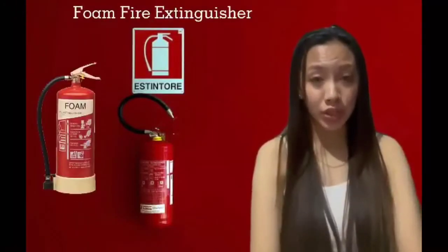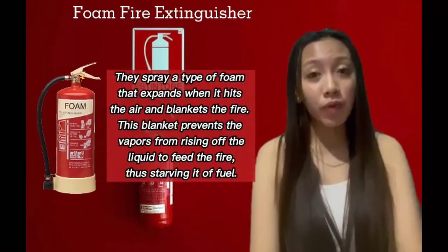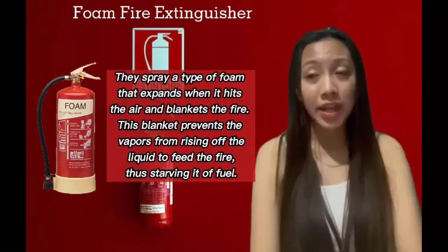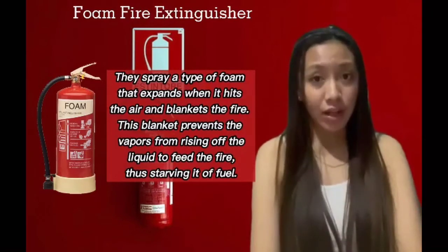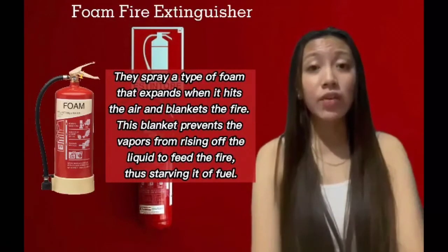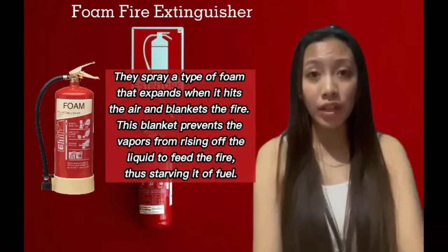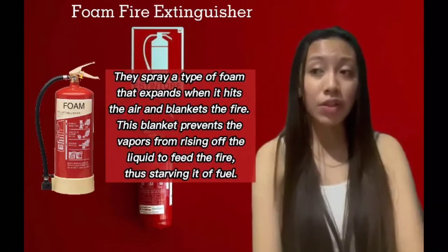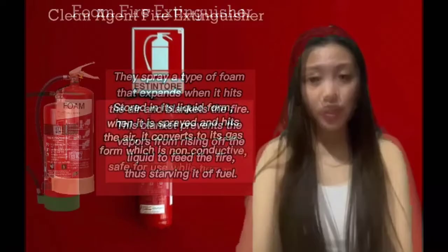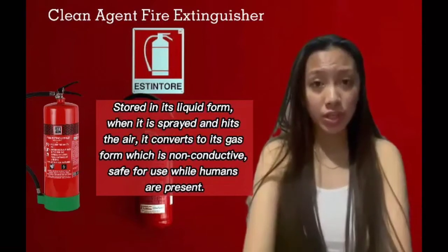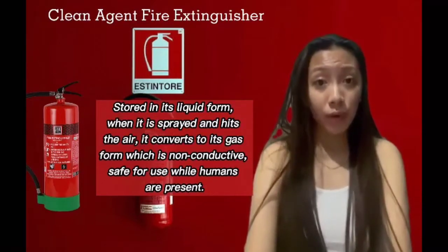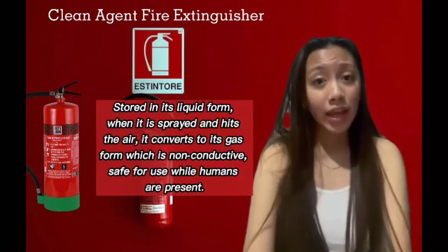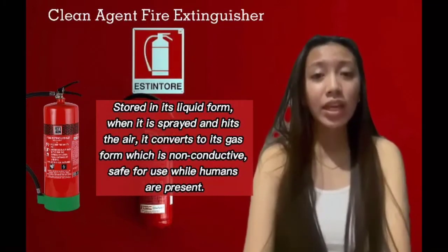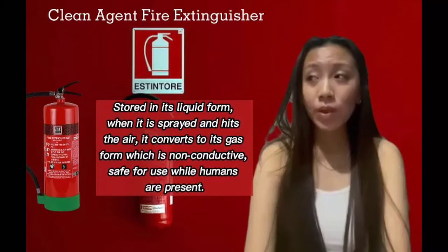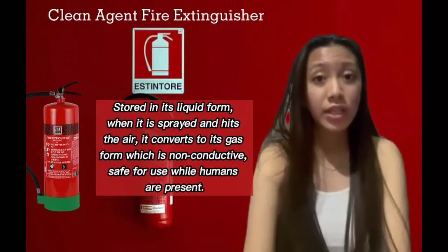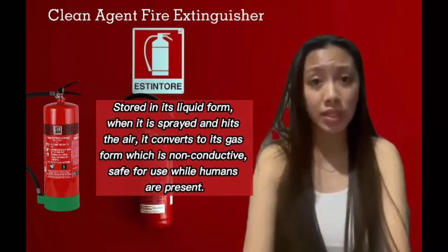Foam fire extinguishers spray a type of foam that expands when it hits the air and blankets the fire. This blanket prevents the vapors from rising off the liquid to feed the fire, thus starving it of fuel. Clean agent fire extinguishers are stored in liquid form. When sprayed and it hits the air, it converts to its gas form, which is non-conductive, safe for use while humans are present.